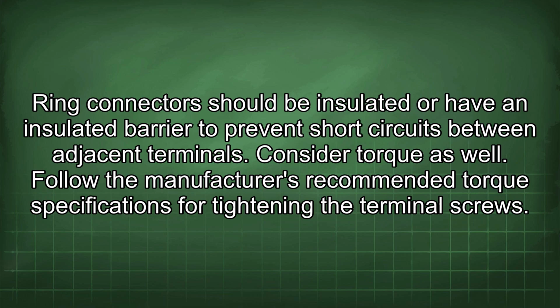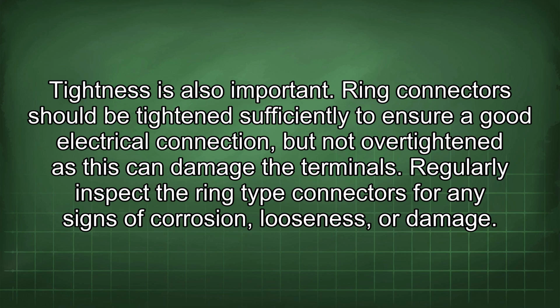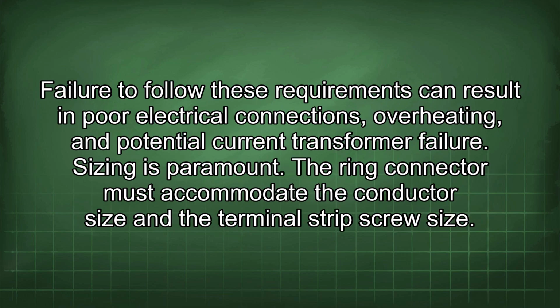Follow the manufacturer's recommended torque specifications for tightening the terminal screws. Tightness is also important. Ring connectors should be tightened sufficiently to ensure a good electrical connection, but not over-tightened, as this can damage the terminals. Regularly inspect the ring-type connectors for any signs of corrosion, looseness, or damage. Failure to follow these requirements can result in poor electrical connections, overheating, and potential current transformer failure.